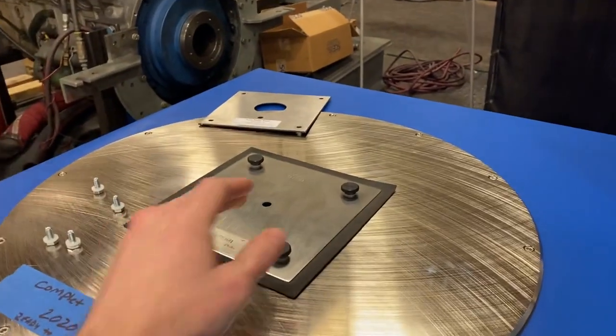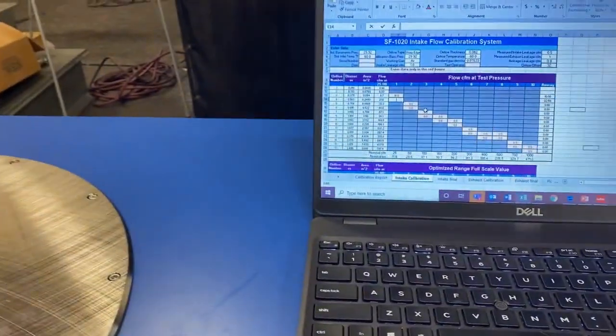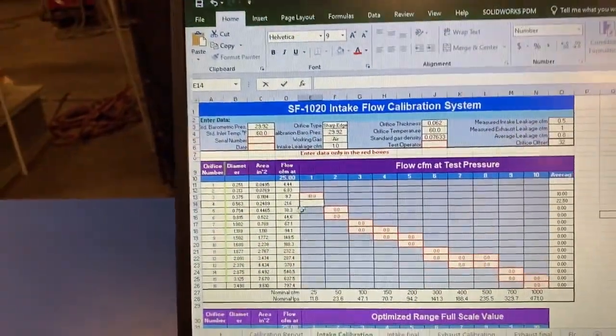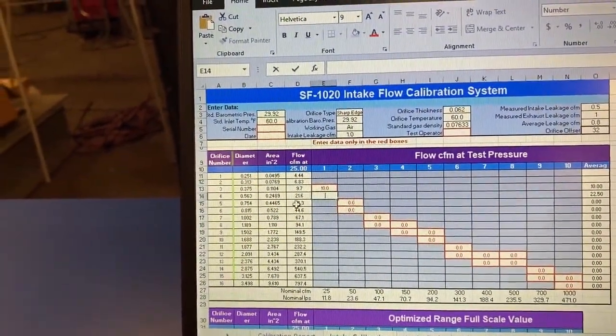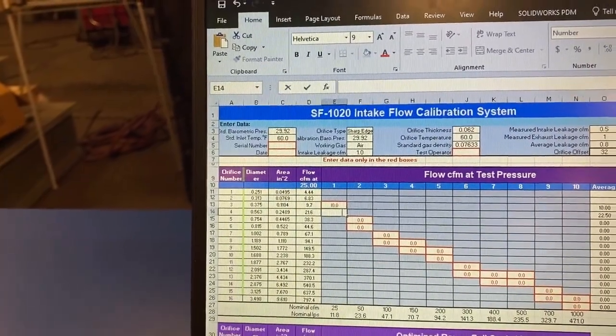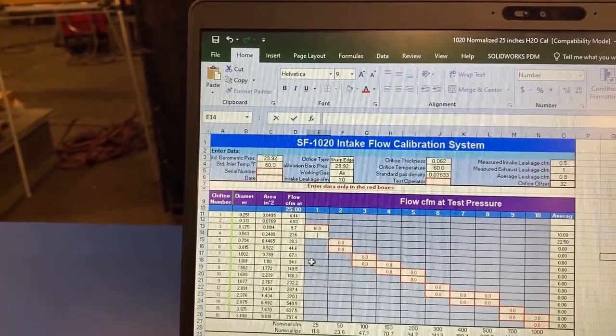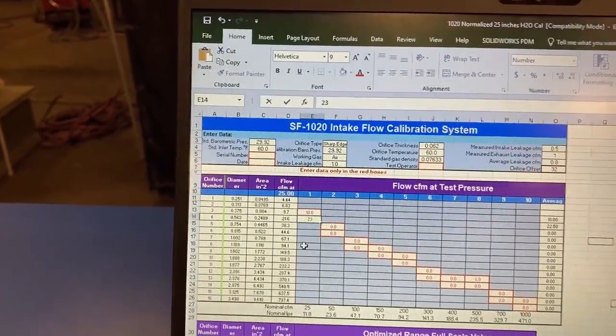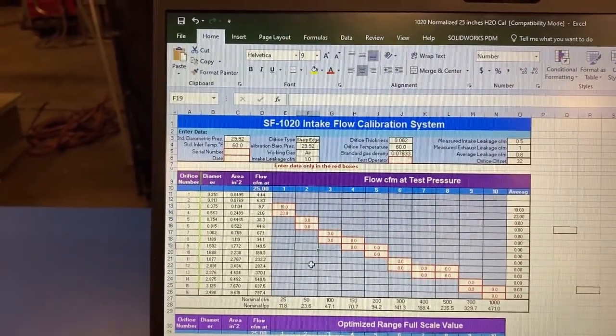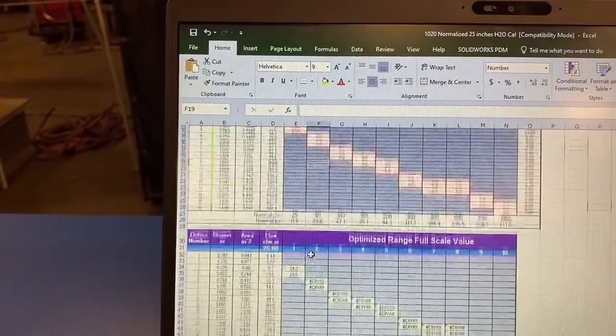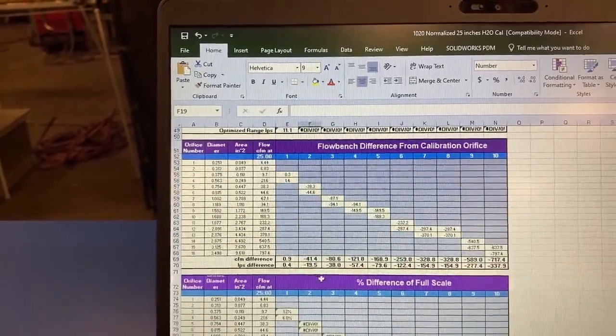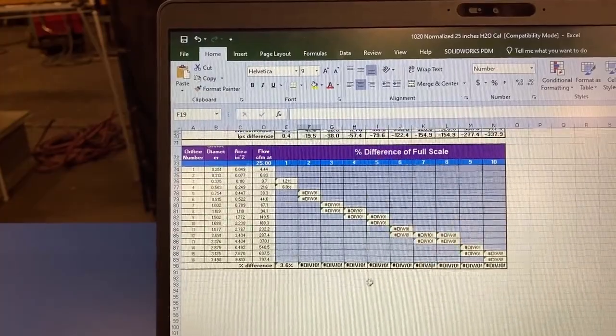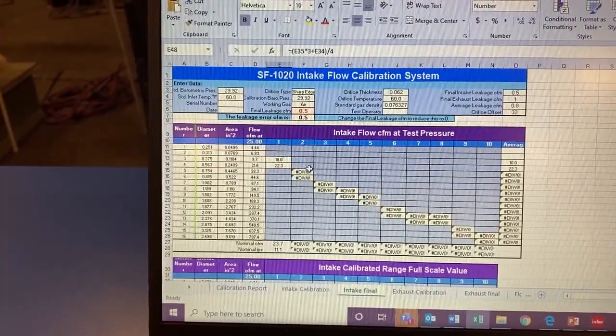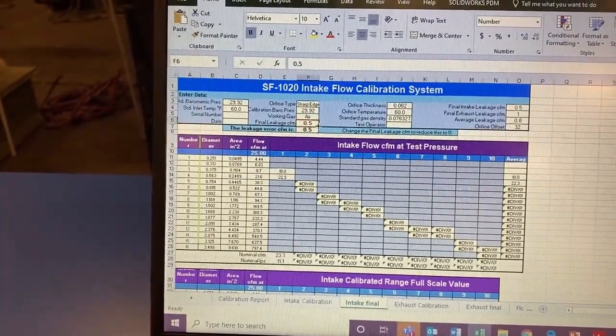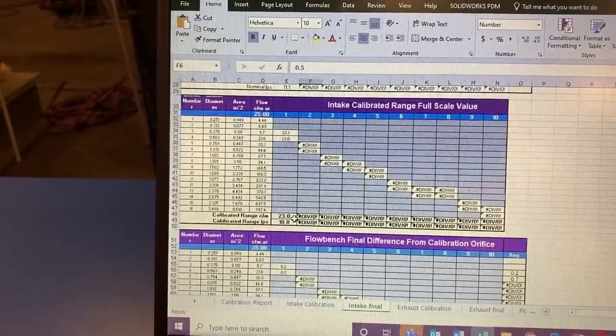Okay, this is still calibration plate 3, but say we changed it to 4 and we flowed it at the same rate. We would expect to get somewhere around 21.6. Let's say we flowed it at 25 inches of water and got 23 CFM. Now this is going to do a calculation and give you a difference. If you come down to intake final, you can see I've changed the leakage to be 0.5, which is more reasonable for this bench.